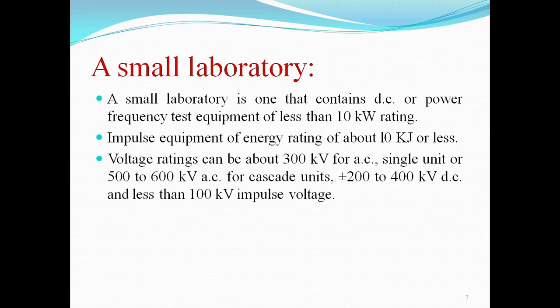So suppose for the small laboratory, either a single unit transformer is available, or as we have discussed in the theory, beyond 300 or 400 kV sometimes we have cascade units of the transformer, and therefore for 500 to 600 kV, two transformers are required.